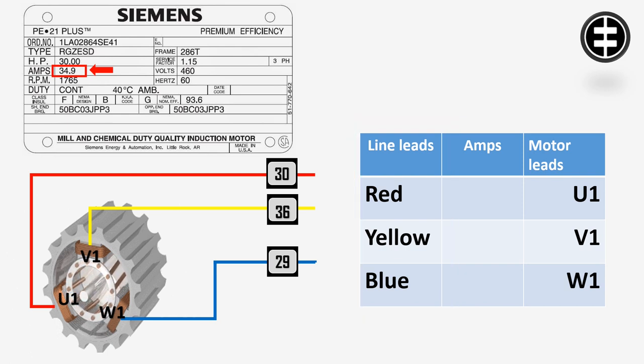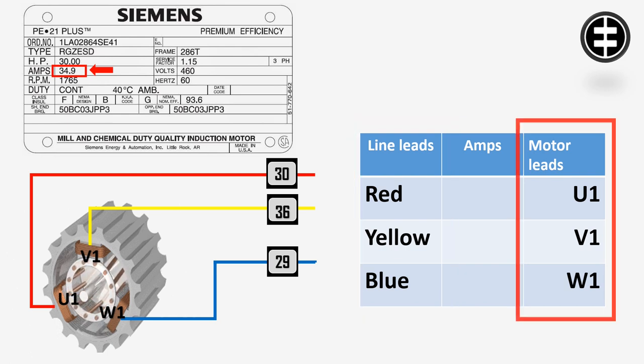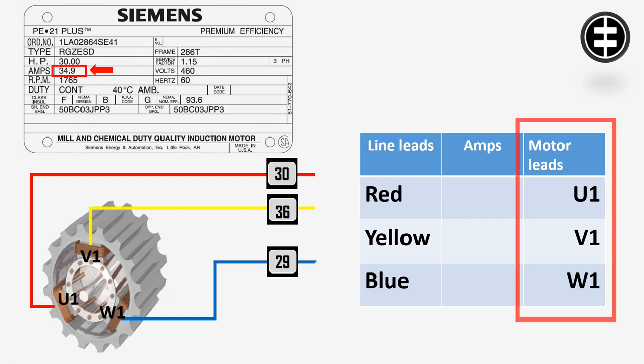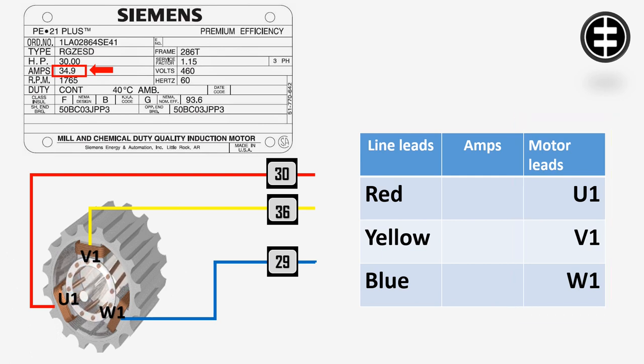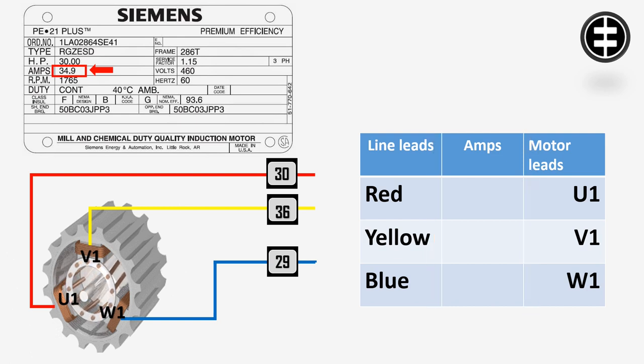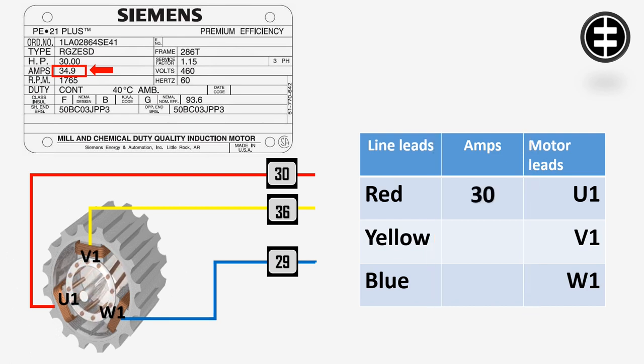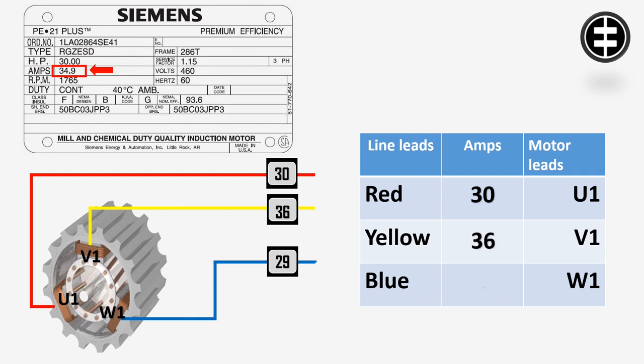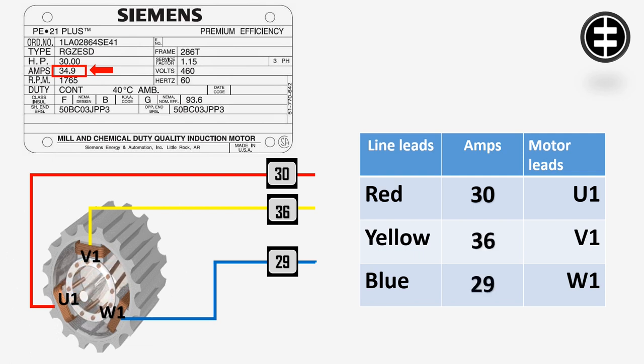In between we will write down the current measurements. First phase draws 30 amps, second phase draws 36 amps, third phase draws 29 amps. So the unbalance is more than 10%.